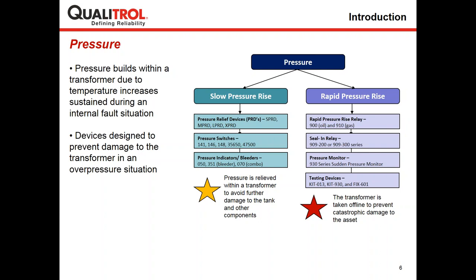This equipment can relieve pressure when it gets to a certain level at your transformer in order to avoid or prevent damage to your transformer or to other components. So it just alleviates that pressure inside of your tank. For a rapid pressure rise, we offer devices that look at when there's a quick change of pressure. And in those cases, a transformer would need to be taken offline in order to prevent any catastrophic damage to your asset. In the next few slides, we're actually going to learn more about the testing devices that we have, or we also call them field test kits, which we offer to look at rapid pressure rise units and ensuring that they work properly in order to protect your assets.